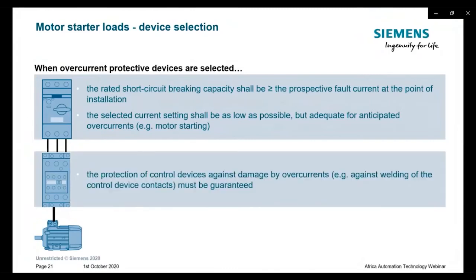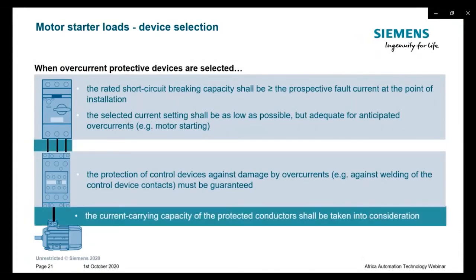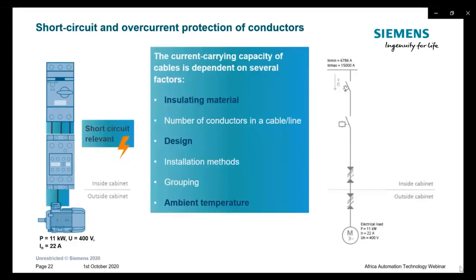The protection of the control devices against damage by overcurrents, for example welding of the control device contacts, must be guaranteed. And the current carrying capacity of the protected conductors shall also be taken into consideration. The current carrying capacity of cables or conductors is depending on several factors. It's the insulating material of the conductor itself.